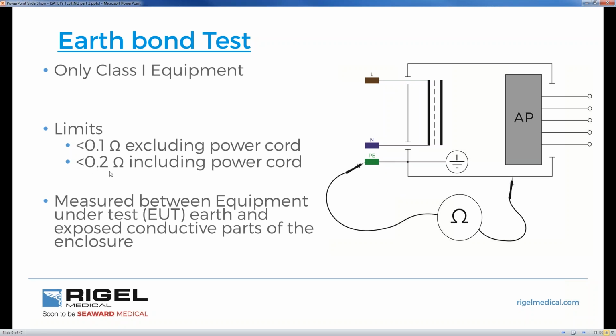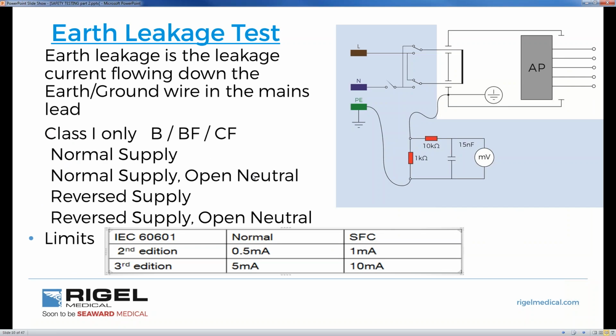These are your pass-fail thresholds as far as 60601 is concerned. So you have less than 0.1 or 0.1 is a good reading, excluding the power cord. If you're using the power cord, then 0.2 ohm is the acceptable pass-fail threshold. Earth leakage. We discussed earth leakage and what earth leakage is in part 1.